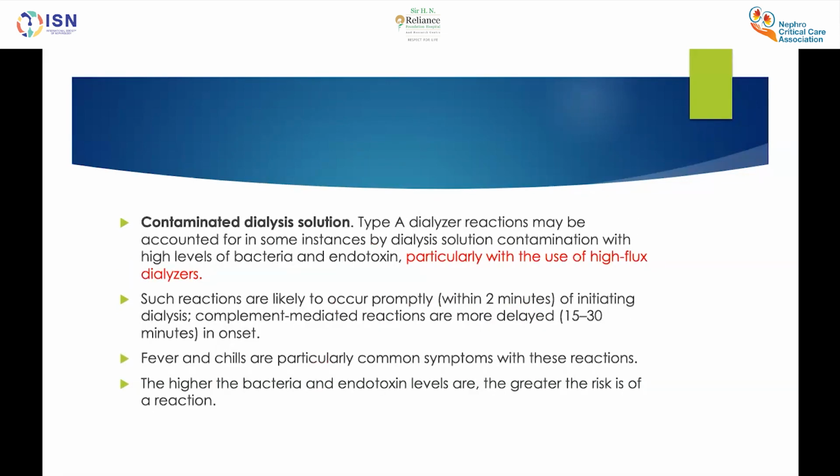There can be a contaminated dialysis solution, which particularly can occur with the use of high flux dialyzers. There can be this dialysis solution contaminated with high levels of bacteria and endotoxin. So these reactions occur within 2 minutes of initiating the dialysis, or it can be a delayed one that is around 15 to 30 minutes after starting the dialysis. So that can be a complement mediated reaction. So the common symptoms are fever with chills, and the higher the bacteria and endotoxin levels, the greater the risk of reaction.